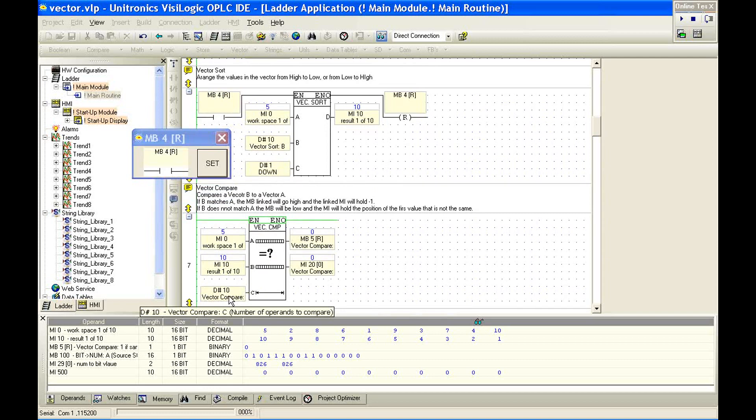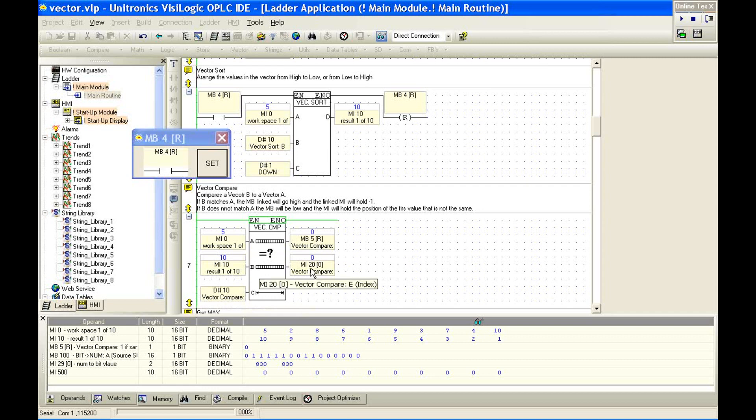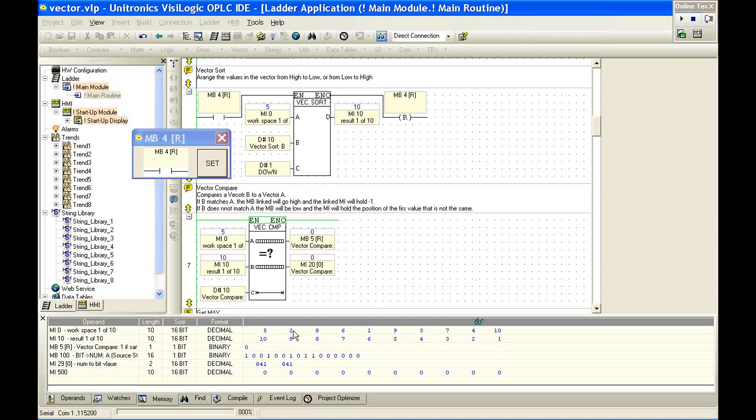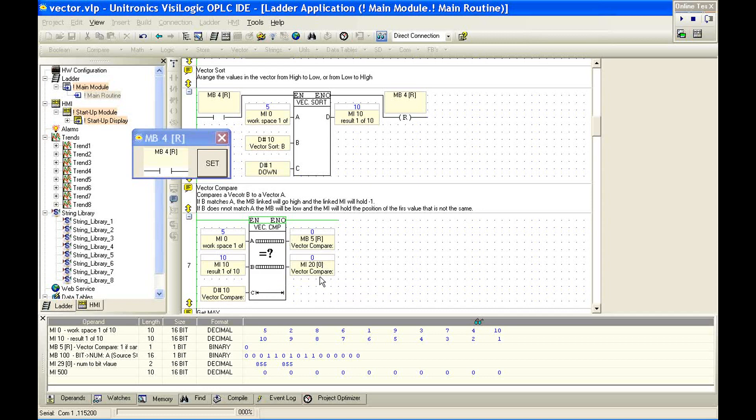If we look at our next function, we have a vector compare. So we've set this up to compare MI0 to MI10 with a length of 10. Our outputs here are MB5 and MI20. You can see we put MB5 down in this workspace. So what we're comparing is this vector to this vector. If they're the same, we should expect that MB5 will be high, and our MI20 will hold the value of negative 1.